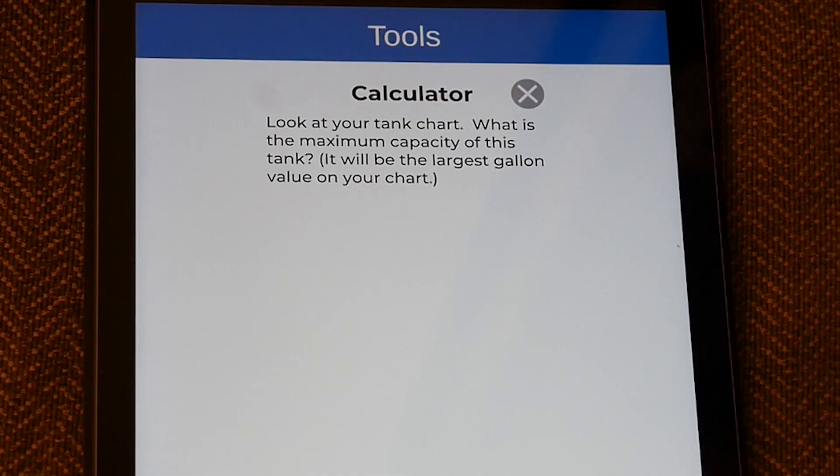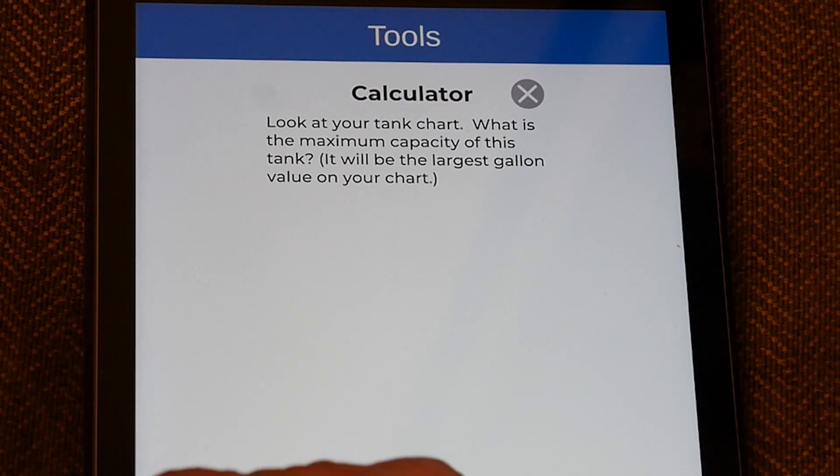I'm going to hit Start and tell the app that the authority having jurisdiction in my area says 95%. It may be 90% — you need to find that out; it's your responsibility. Next, it says: look at your tank chart — what is the maximum capacity of this tank? We know we've got a 15,000-gallon tank, but 15,000 gallons is not the exact amount that tank can hold.